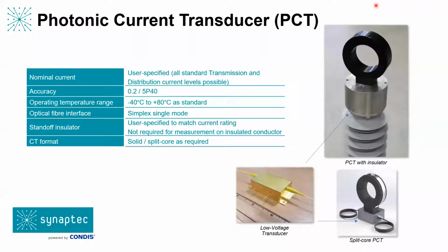Now we have a range of sensors, and just to give you an example of what those are like. Our current sensor, we call our photonic current transducer, or PCT. We can measure protection or metering class systems separately. At the moment, we can't do protection and metering in one current sensing device, unlike what we can do for voltage. But the key thing here is that this is a very robust sensor. It's fiber in, fiber out. It can deal with operating environmental temperature ranges from -40 to +80 as standard. This is because, as part of the technology, the sensor knows its own operating temperature all the time, and it self-calibrates for that. So we don't have to resort to any passive temperature compensation. It measures its own temperature constantly and adapts to that, which means that we can cope with huge temperature swings over the year, for example, in Norway and the Middle East.